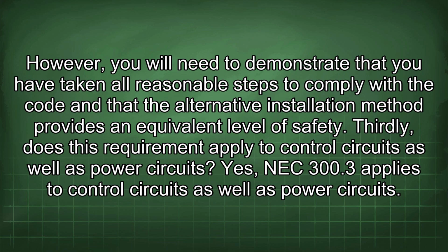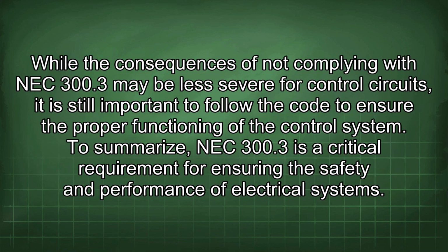Thirdly, does this requirement apply to control circuits as well as power circuits? Yes, NEC 300.3 applies to control circuits as well as power circuits. While the consequences of not complying with NEC 300.3 may be less severe for control circuits, it is still important to follow the code to ensure the proper functioning of the control system.